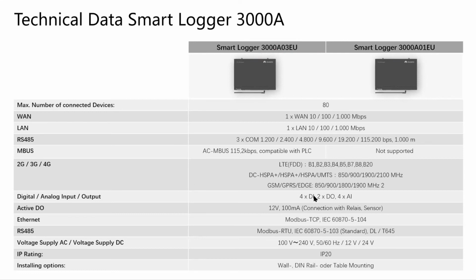Other features, you have 4 digital inputs, 2 digital outputs, and 4 analogical inputs. You have an active digital output of 12 volts and 100 milliamps. You have Modbus TCP protocol and IEC 104. And for southbound, so communication with inverters, you use the Modbus RTU protocol or the IEC 103 protocol. The rating of the smart logger is IP20, so it cannot be installed outdoors. You need to install it inside some premises.